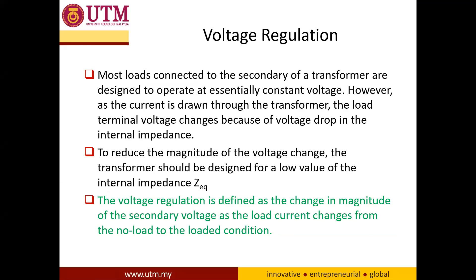As the current is drawn to the load, the terminal voltage of the transformer will change because of the voltage drop in the internal impedance, meaning that the voltage across the terminal load of the transformer changes. For example, when there is no load, the voltage here is what we call V no-load — maybe 200 volts. But when you connect the load terminal with a load, there is some voltage drop.